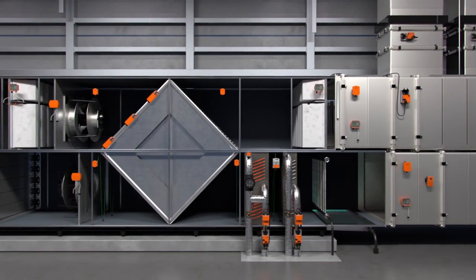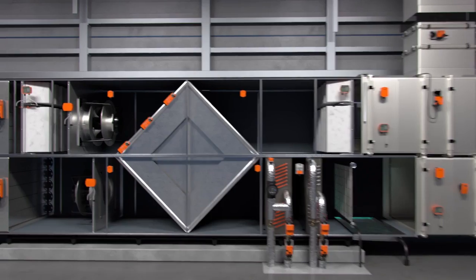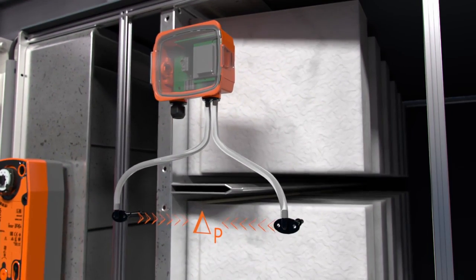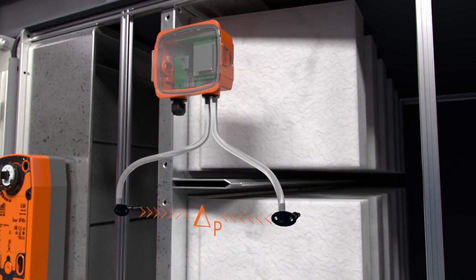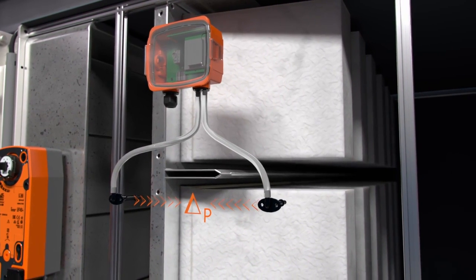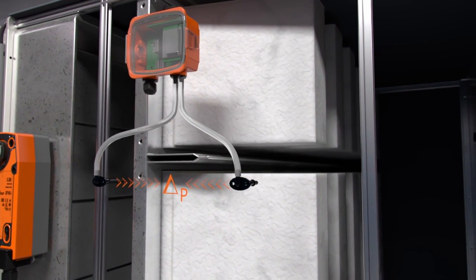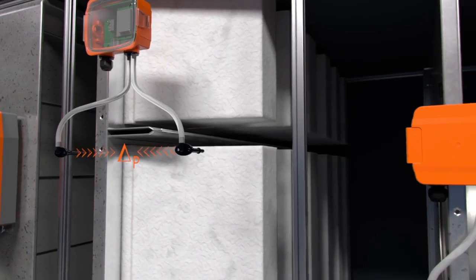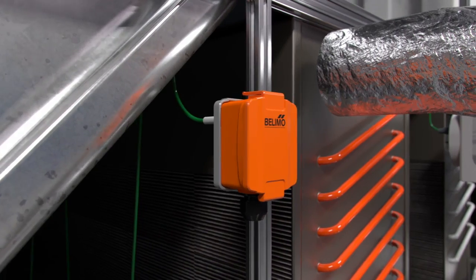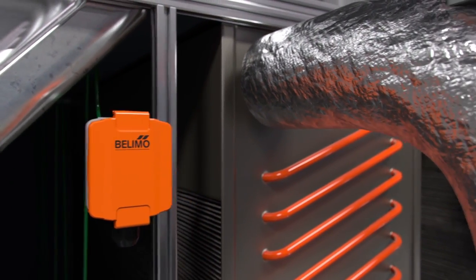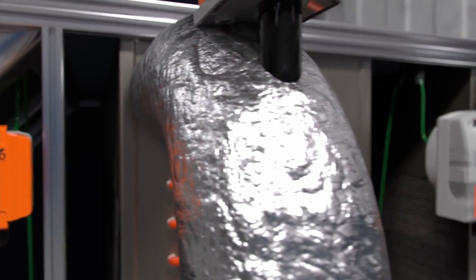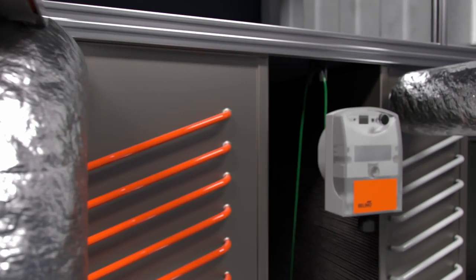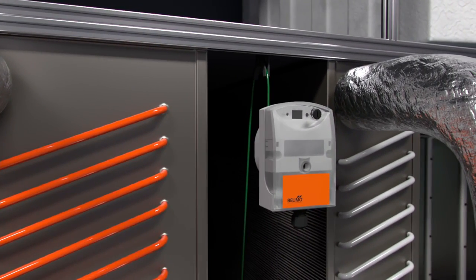Various sensors measure the physical conditions of the air in the air handling unit and pass the information on to the controls. Important sensor types are differential pressure sensors, which, for example, measure the pressure difference across the filter or across the fan. From these values, the degree of filter clogging or the flow rate of the fan can be determined. Temperature and humidity sensors measure the air conditions and help the air handling unit to condition the air accordingly or serve to monitor the individual measured values in the event of a fault.